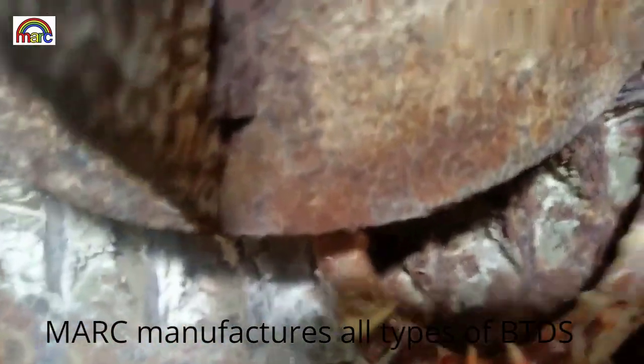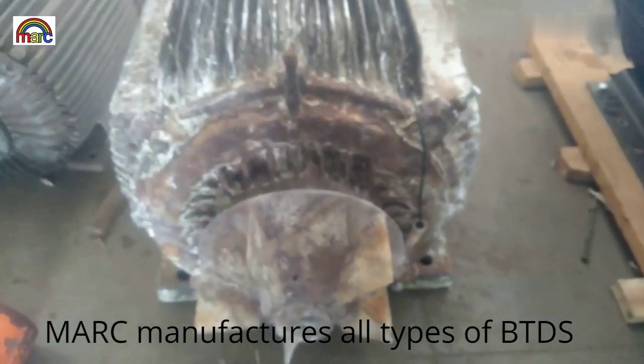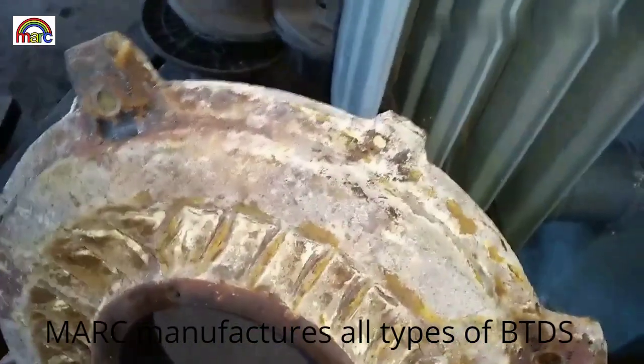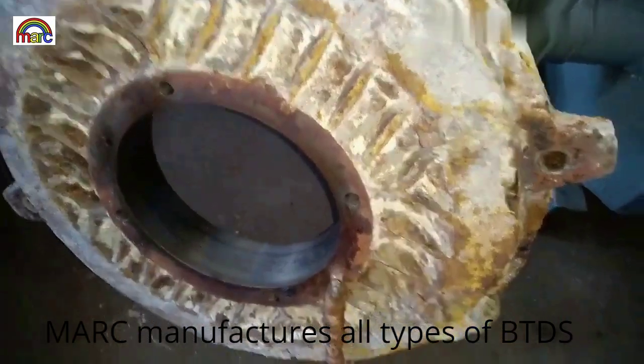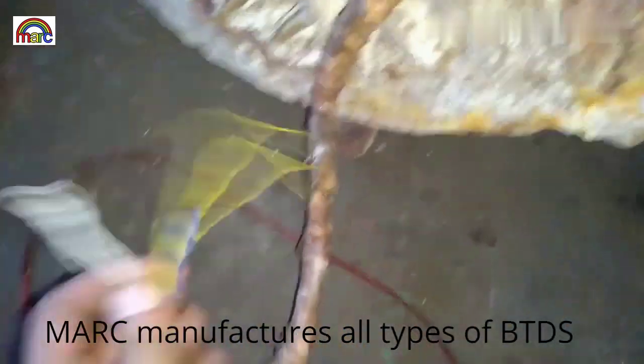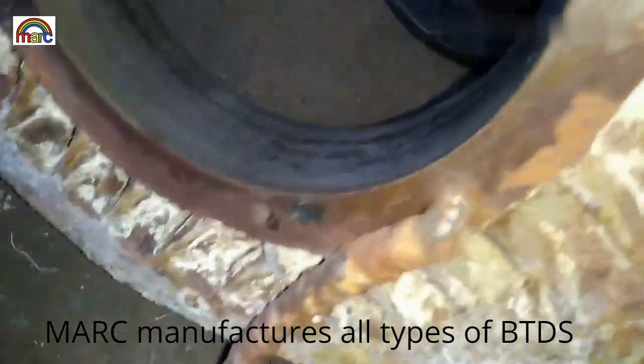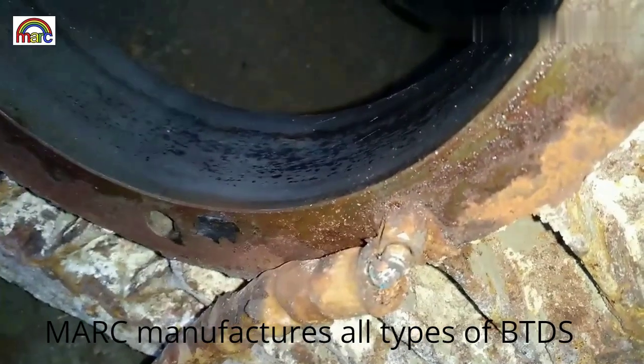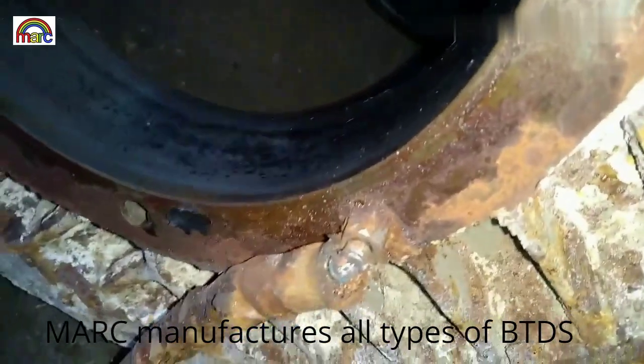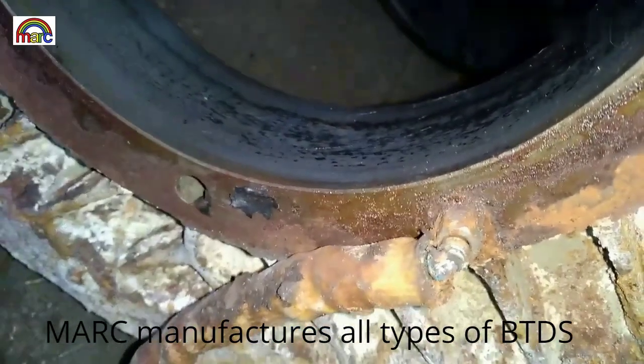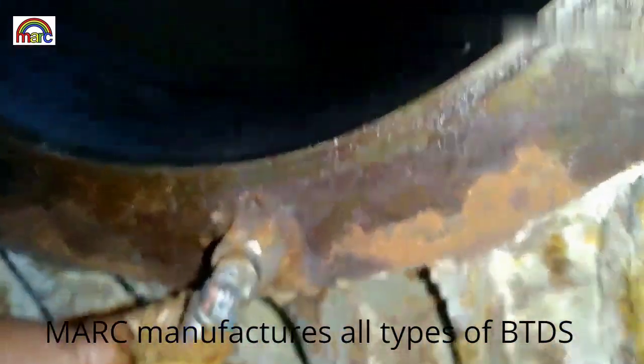As per the wiring we just traced out, the BTD is mounted on the non-drive end side below the cooling fan. You can see this is the fan, and behind that is the bearing and bearing housing. Your BTD is mounted on the bearing housing with the help of probes. When the bearing is placed on the housing, all the temperature generated by the bearing is transferred to the housing, and from the housing it is transferred to the BTD.